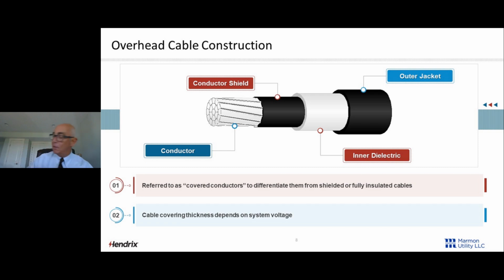The third layer is what we call the outer jacket. That's where all the tricks are. It's a high density polyethylene. We source the highest high density polyethylene we can because we want abrasion resistance. There is the anticipation that the conductor someday is going to touch a tree or rub on a tree branch. We don't want to have abrasion, so we want very high abrasion resistance.